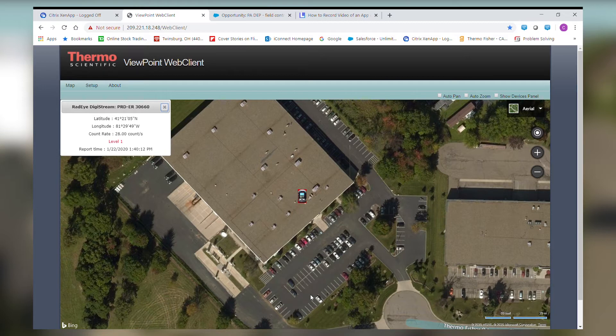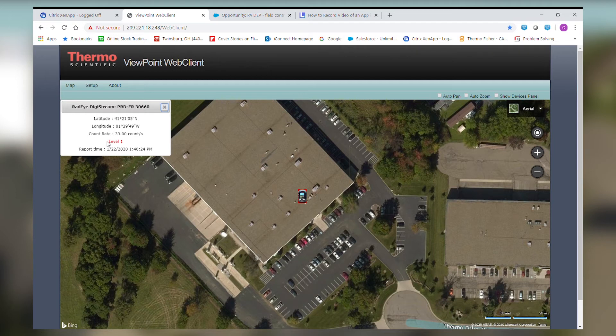You can also see the information in the window has changed to a level 1 alarm, with the red level 1 text now displayed. All these things, including the colors of the icon and what is displayed in the window, are all configurable. You can see the counts are changing and they currently read 33 counts per second, displaying a level 1 alarm.